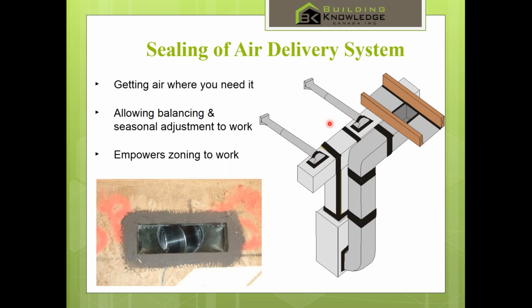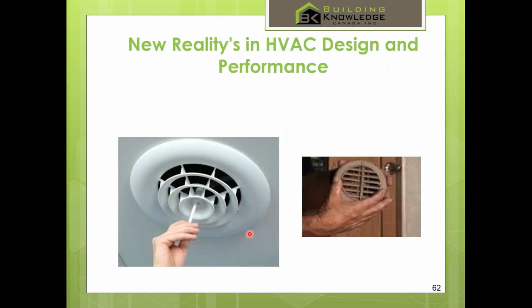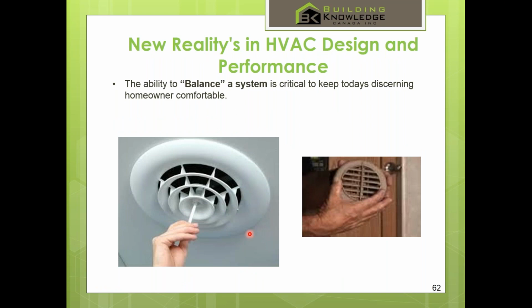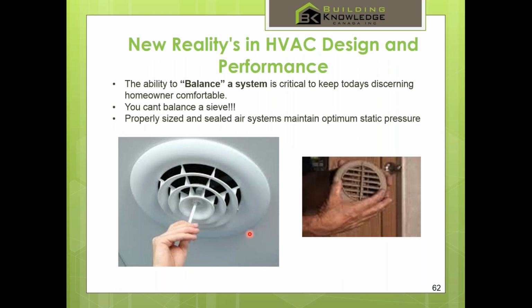Sealing of these systems is incredibly important. When you have low CFM systems, low continuous movement of air, you have to make sure that you maintain good static pressure or it's never going to get to the longest run. So sealing the ductwork is incredibly important. When you seal ductwork, it makes balancing the system effective. If you try to balance a duct system that's leaking, it's like trying to plug the holes in your garden hose so you get more flow out the end, and we know from fluid dynamics and mechanics that that doesn't work. It just simply goes out the other holes first. You can't balance a sieve, like we say.